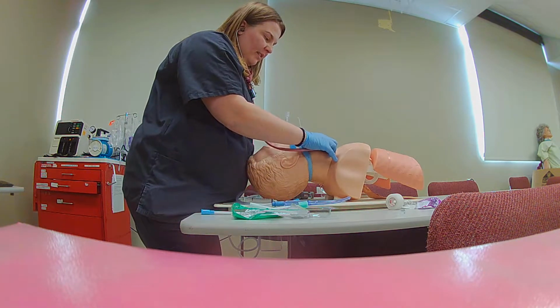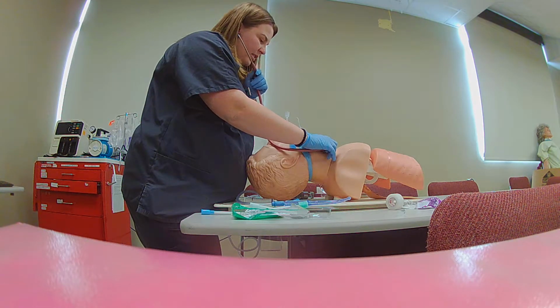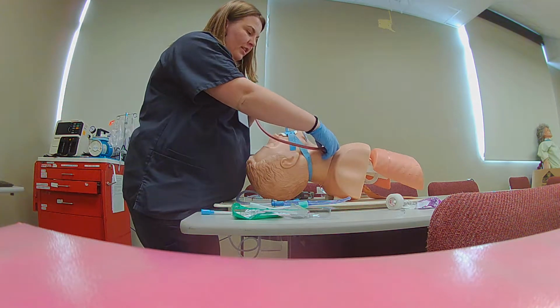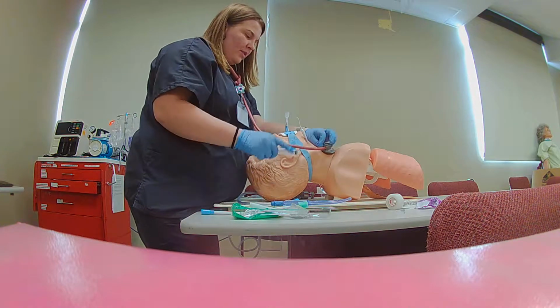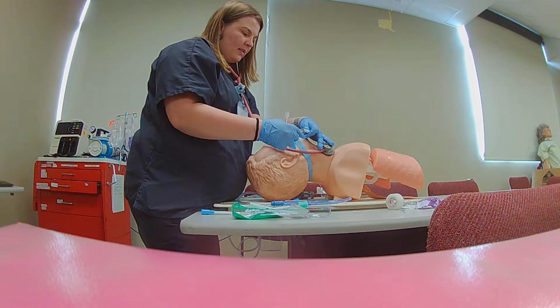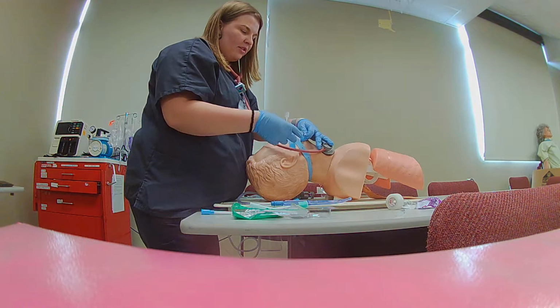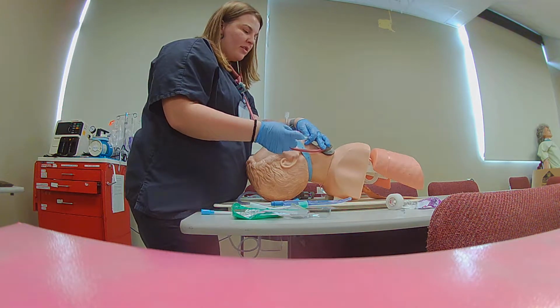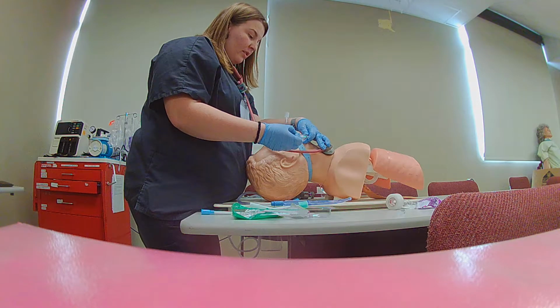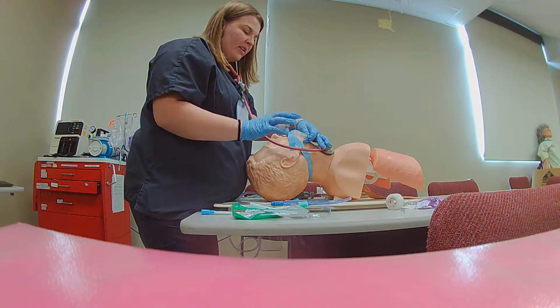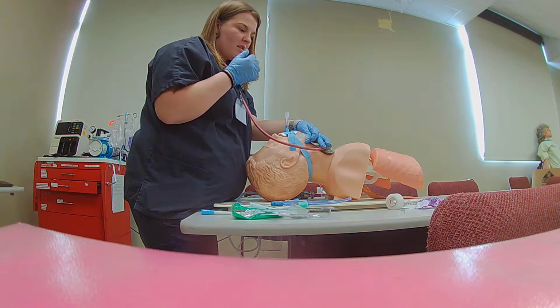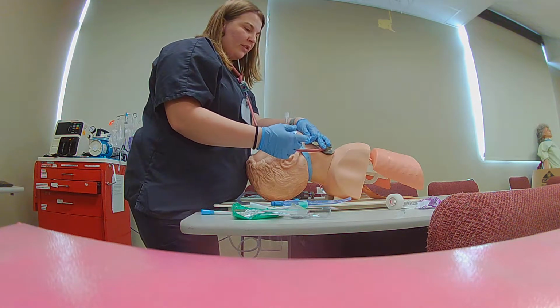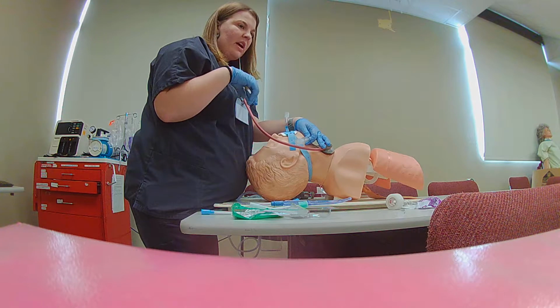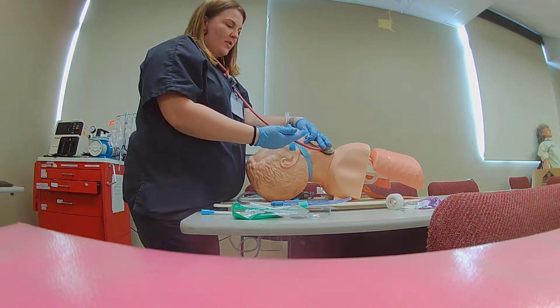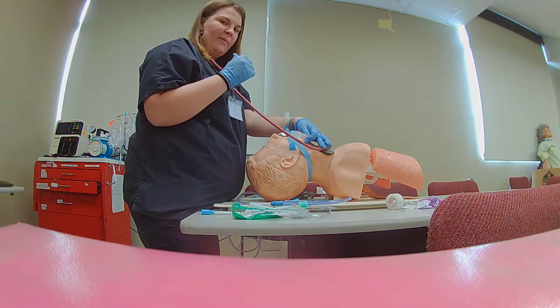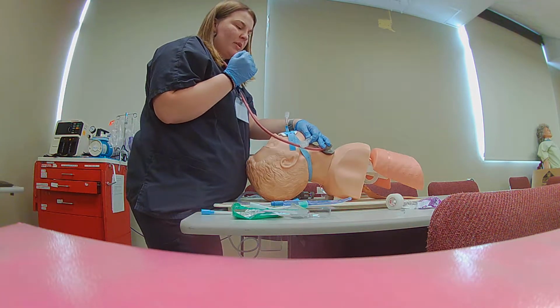listening for a leak on the patient's neck during inspiration, and you would slowly, to make sure it's not too high of a pressure, just slowly remove some air and continue to listen for the leak. As you do it, at the first little leak that you hear, you then put a little bit of the air back in, and that's your minimum cuff pressure that you can keep to keep it occluded.